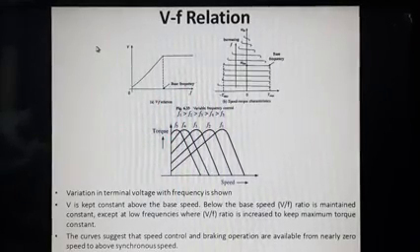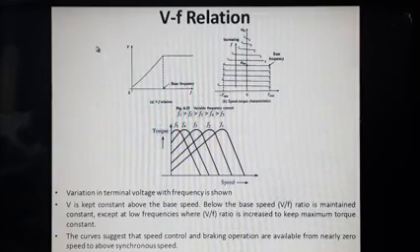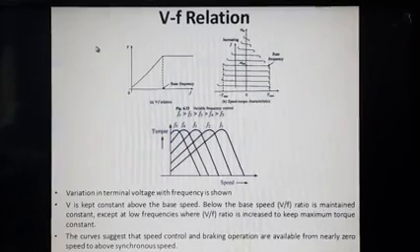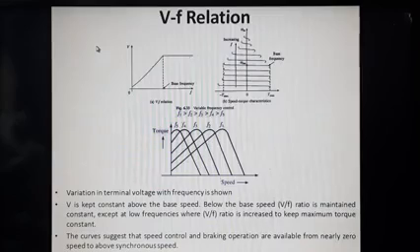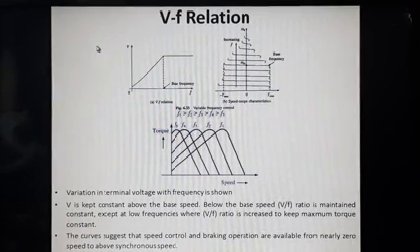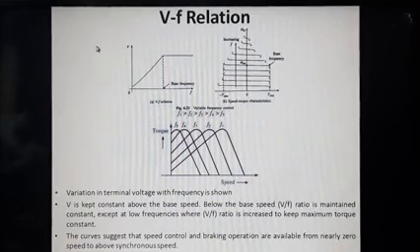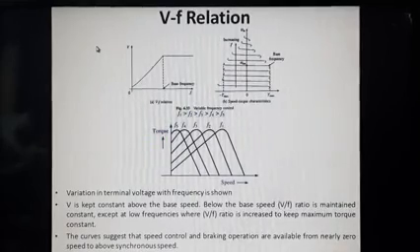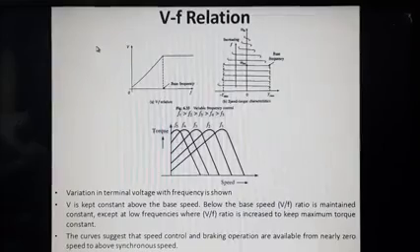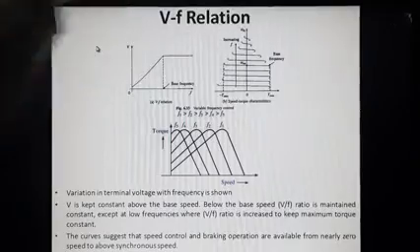So another problem which you will be facing here is, this particular method of speed control can be achieved only for speed control below the base speed. If you want to achieve speed control above base speed, this method is not a practical one, because you won't be able to increase the voltage above the rated value. So when you are trying to increase the frequency, the value of voltage has to be retained at the rated value itself. So the V by F value will be decreasing, and the Tmax value also will be decreasing above the base speed. That's why this graph is showing this behavior.